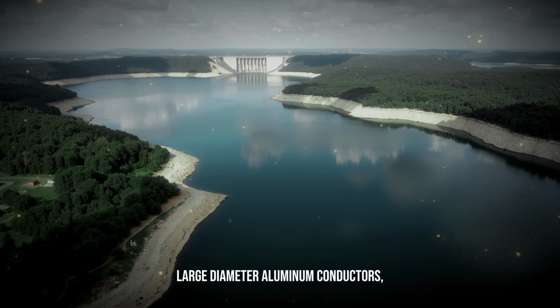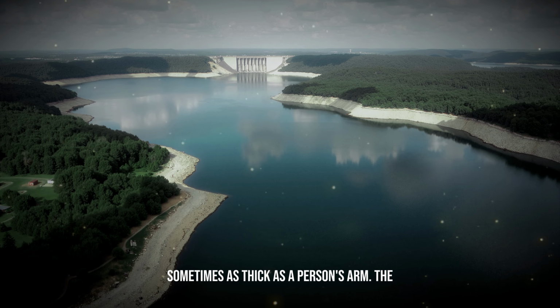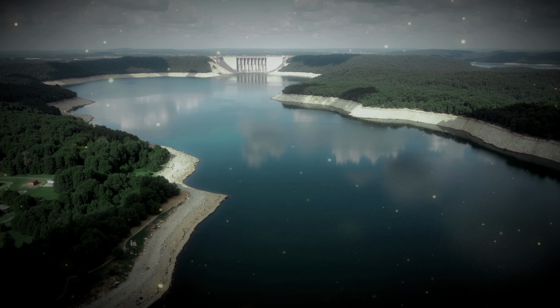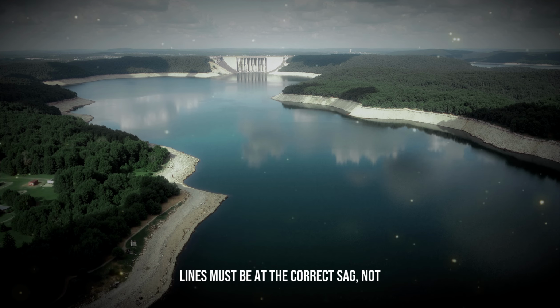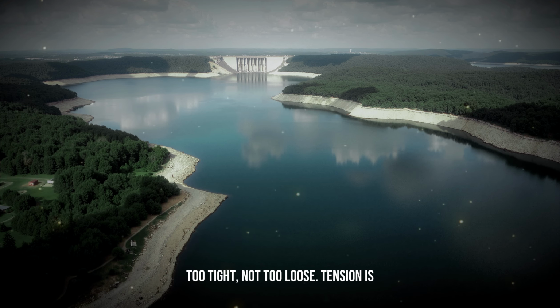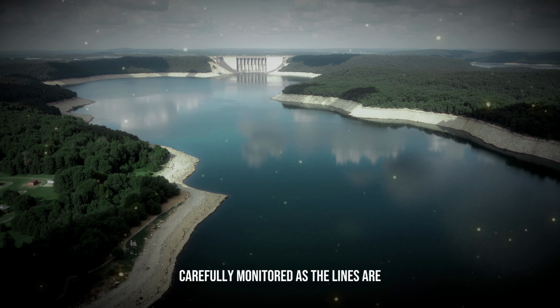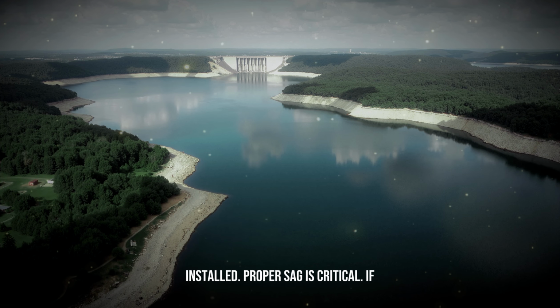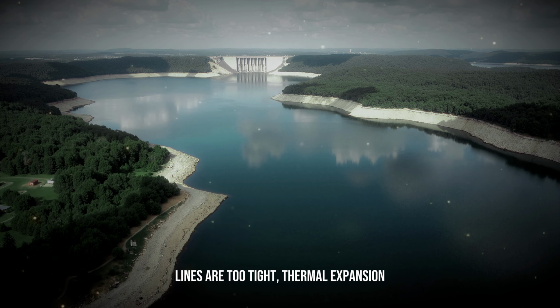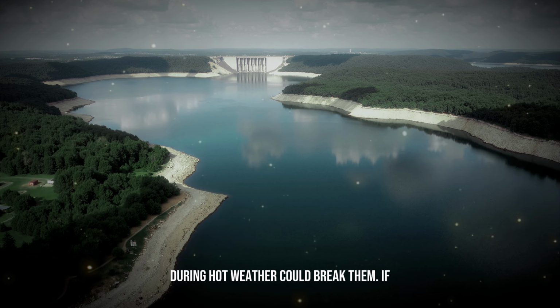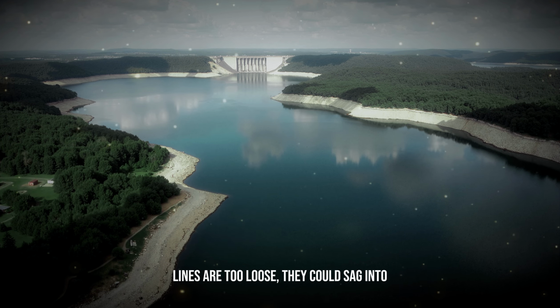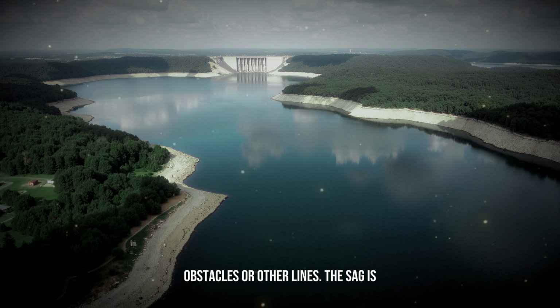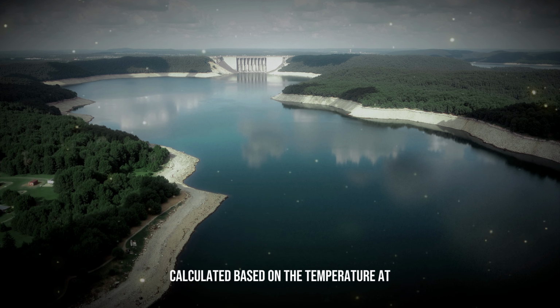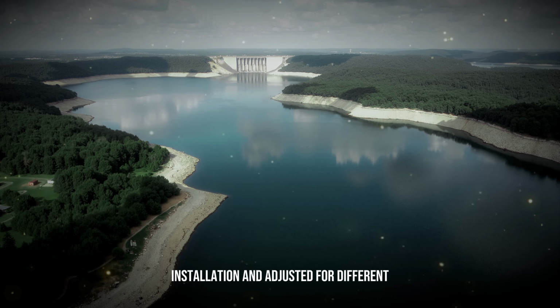The lines are large diameter aluminum conductors, sometimes as thick as a person's arm. The lines must be at the correct sag, not too tight, not too loose. Tension is carefully monitored as the lines are installed. Proper sag is critical. If lines are too tight, thermal expansion during hot weather could break them. If lines are too loose, they could sag into obstacles or other lines. The sag is calculated based on the temperature at installation and adjusted for different weather conditions.